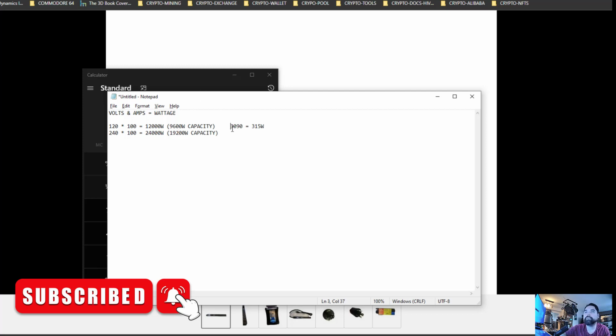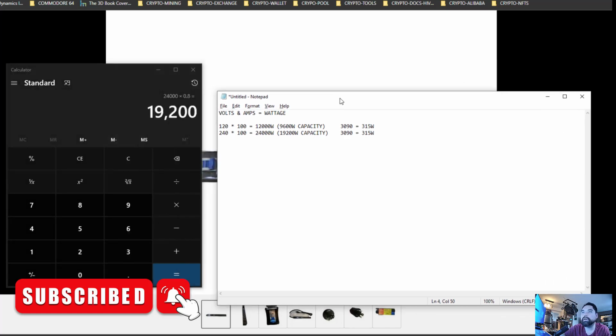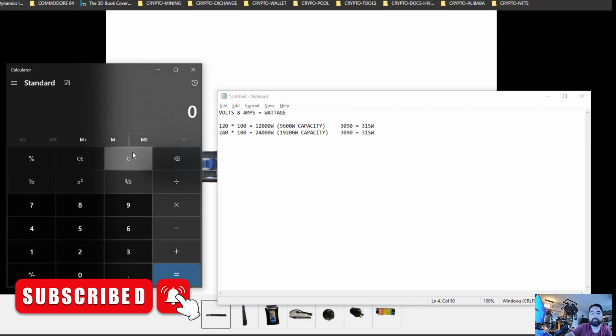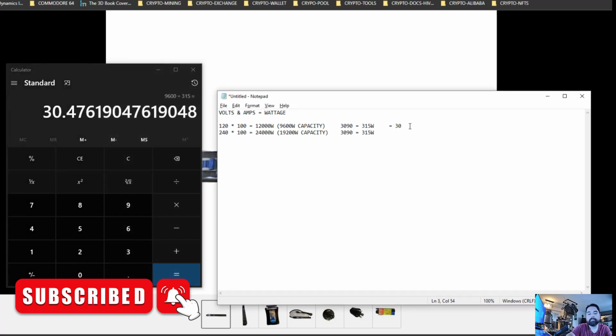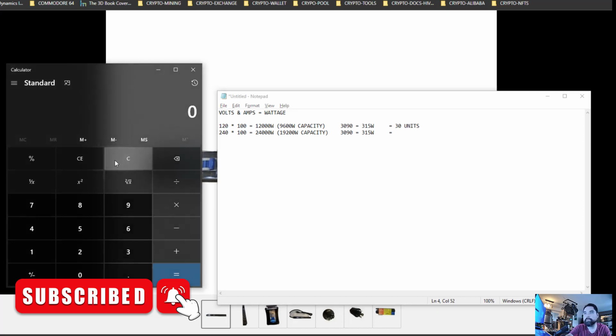So a 3090 takes up 315 watts. Pop quiz: how many 3090s can you run on 120 volts at 100 amps, versus 240 volts at 100 amps? The answer is the usable wattage divided by 315. At 120 volts, with 9,600 watts, you can run 30 units. At 240 volts, with 19,200 watts, you can run 60 units.